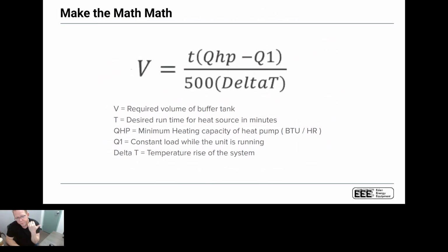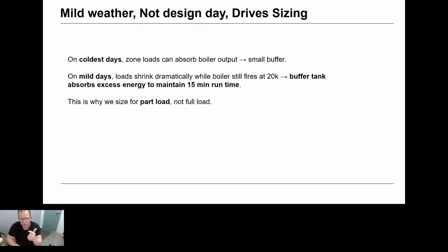So as far as the formula for how we size the buffer tank around that air-to-water heat pump, it's important that we understand that the volume of that buffer tank is dictated by what is our desired runtime and how much are we going to allow that unit to swing. So what are the BTUs that are going into it? What is that constant load? And what is the minimum heating capacity of that heat pump? So this is a very universal formula that you would use for sizing buffer tanks, whether it's an air-to-water, water-to-water. It doesn't matter if it's a gas boiler, it's all the same.